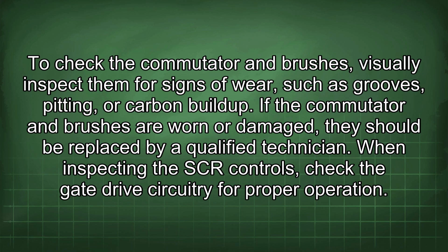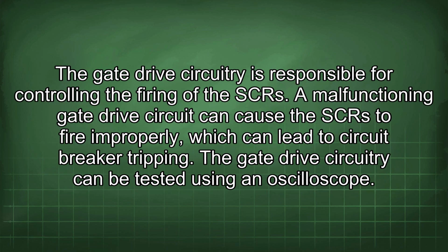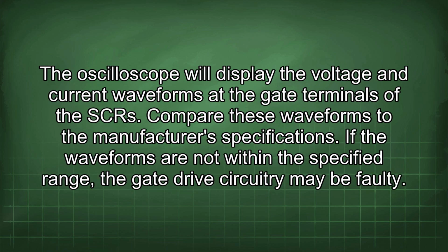When inspecting the SCR controls, check the gate drive circuitry for proper operation. The gate drive circuitry is responsible for controlling the firing of the SCR. A malfunctioning gate drive circuit can cause the SCR to fire improperly, which can lead to circuit breaker tripping. The gate drive circuitry can be tested using an oscilloscope. The oscilloscope will display the voltage and current waveforms at the gate terminals of the SCR. Compare these waveforms to the manufacturer's specifications. If the waveforms are not within the specified range, the gate drive circuitry may be faulty.